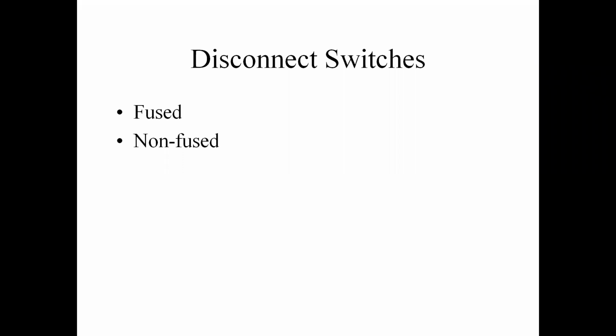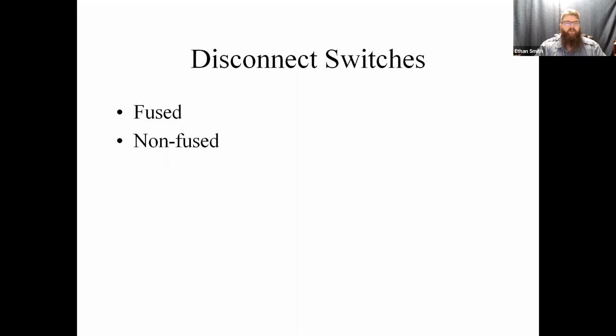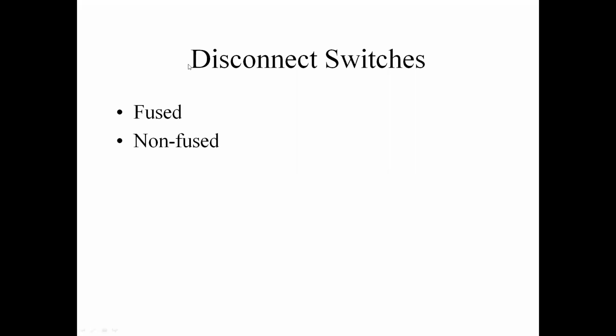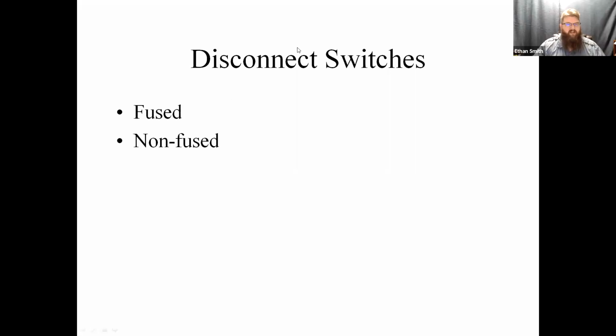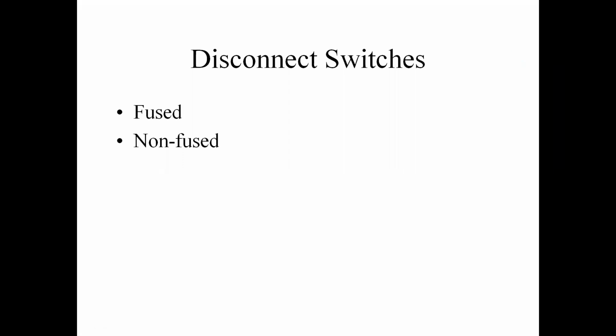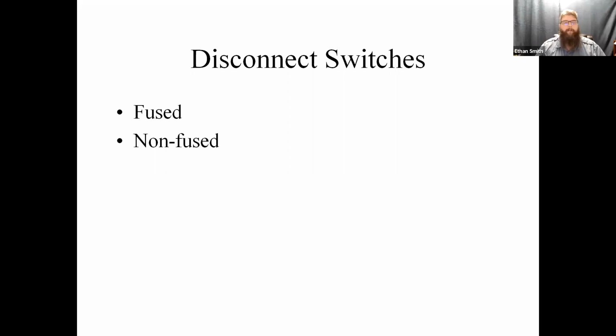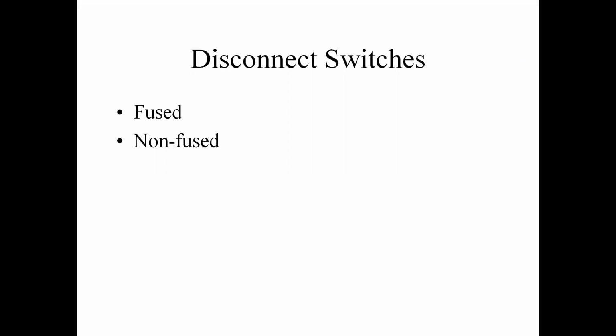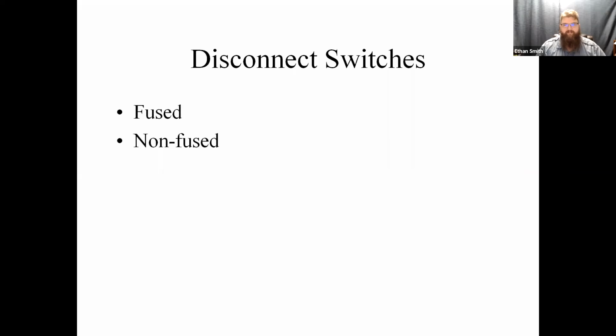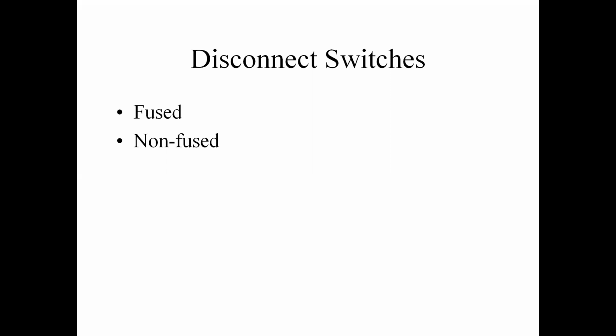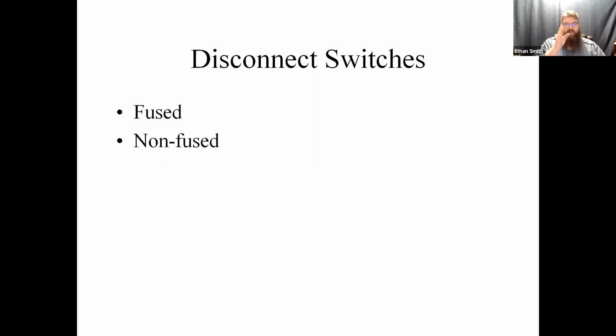Yes. Okay. What are breakers for? To turn on and off the power. Okay, that's one purpose of them, so they can be a disconnect switch. What else are breakers for? Too much current. If you have too much current going through what? The load. Nope, they don't care about the load. Breakers are there to protect the wire. That's what breakers are designed to do. They're there to make sure that the load connected to the wire doesn't draw enough current to make the wire ignite.